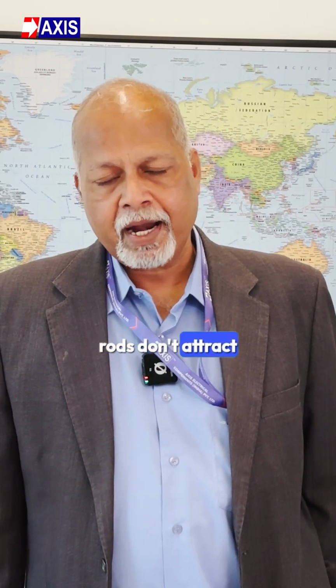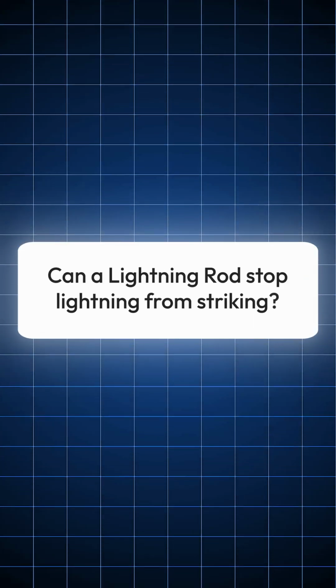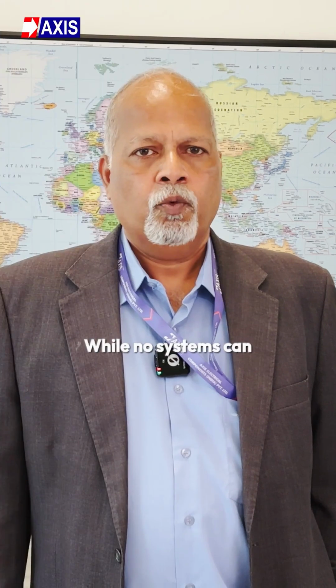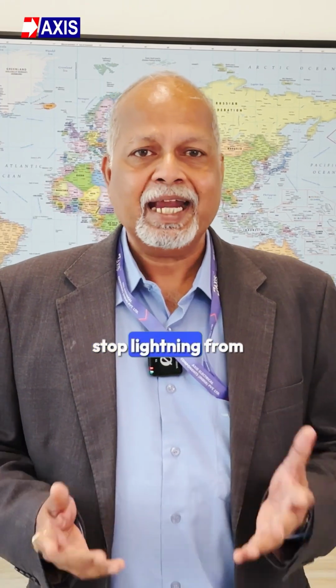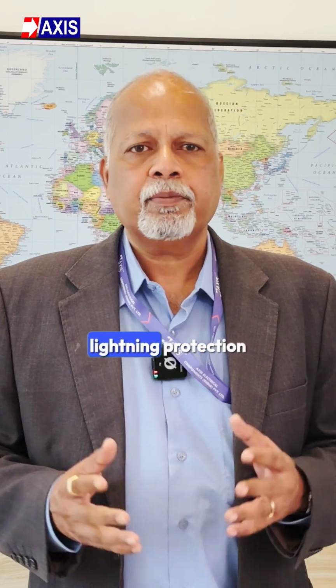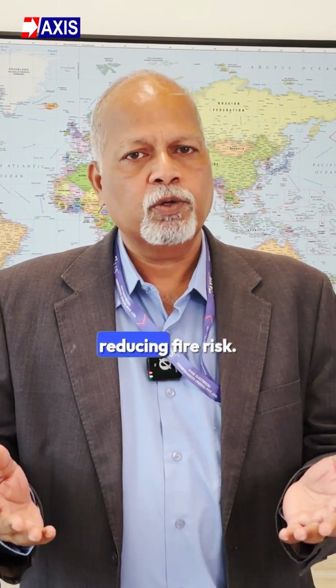No, conventional lightning rods don't attract lightning. They provide a safe path for lightning impulse current to flow, preventing damage to structures. While no system can stop lightning from striking, a properly installed lightning protection system directs the lightning impulse current safely to ground, preventing damage to your property and electrical systems, and reducing fire risk.